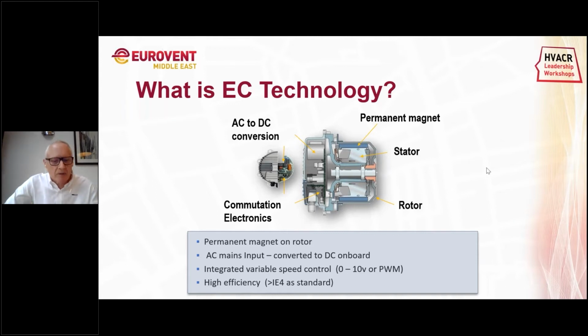Brushless DC motors have been around for years, but they always needed a separate DC supply. So in applications where you only have AC supply, this introduced a lot of added cost and, to be honest, quite a complex situation. With EC fans, it's got integrated electronics, so they're connected directly to an AC supply. In addition to performing the commutation, the electronics convert AC to DC and control the fan speed by regulating the power to the motor.